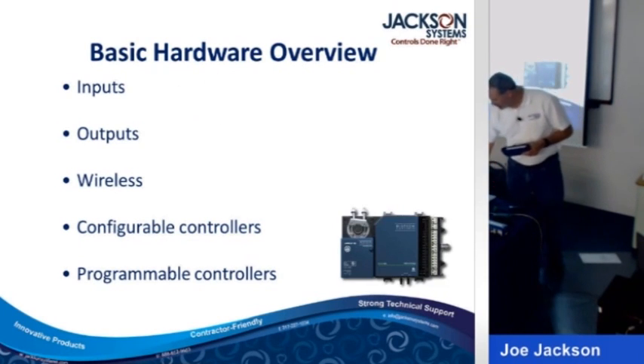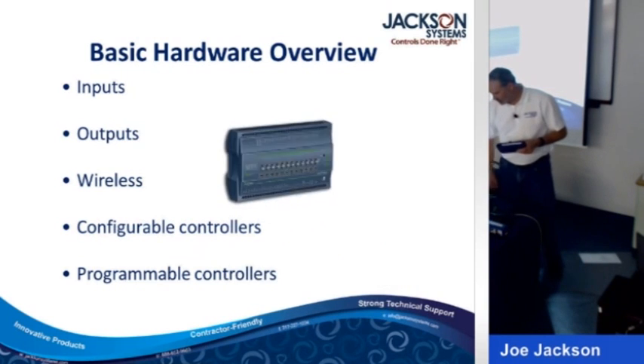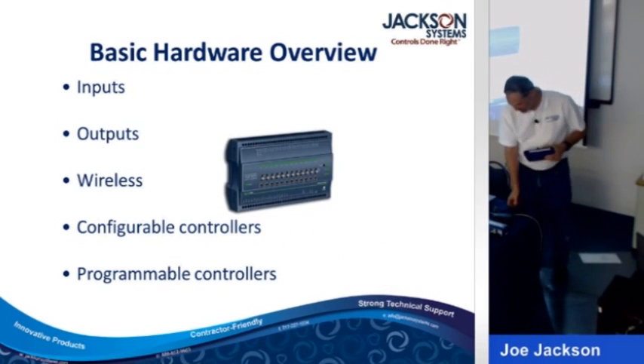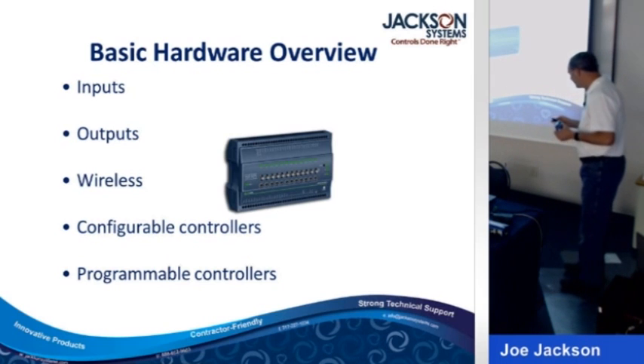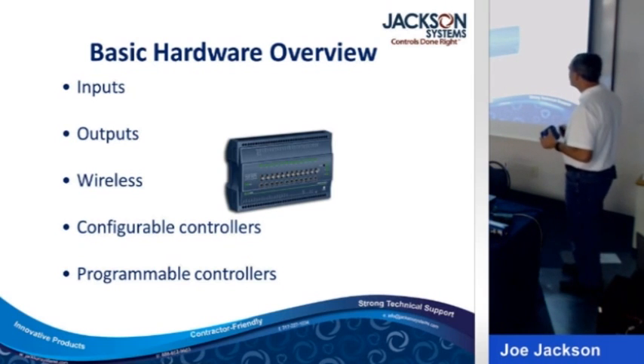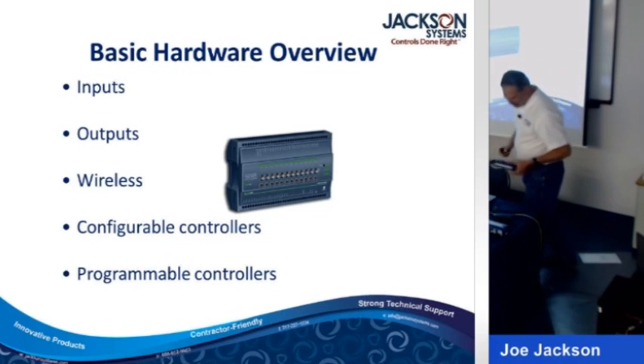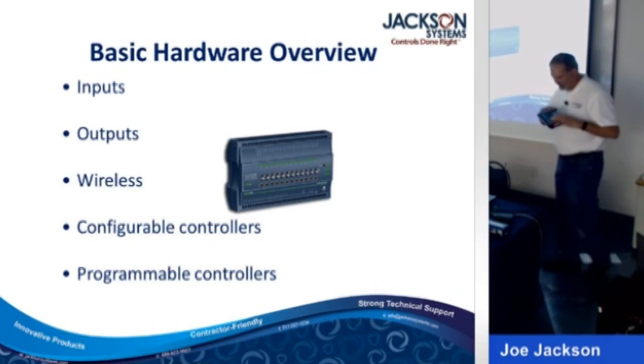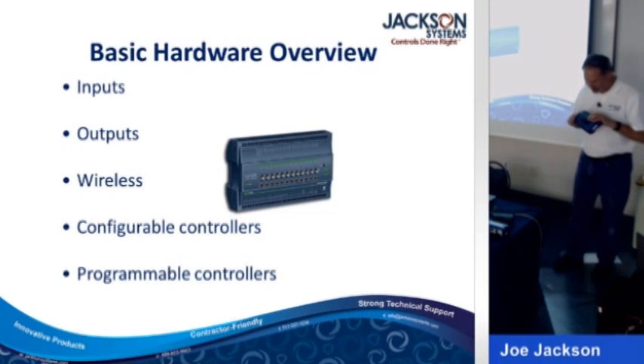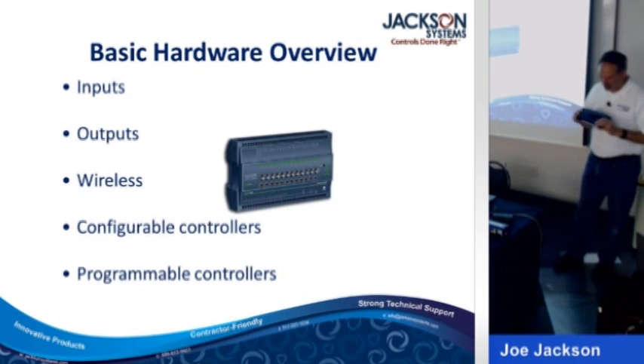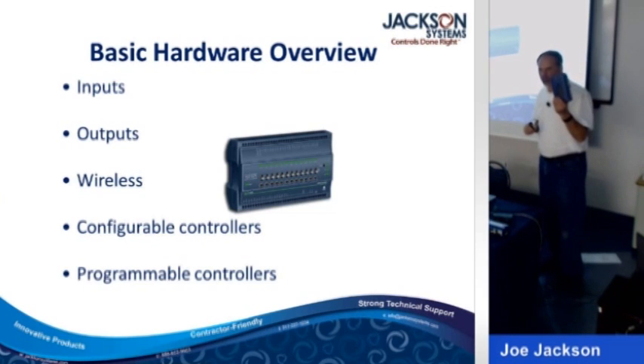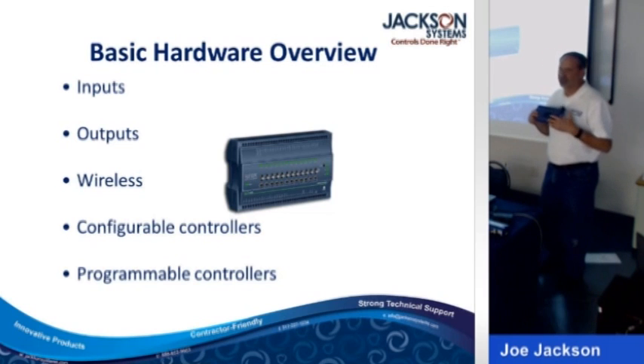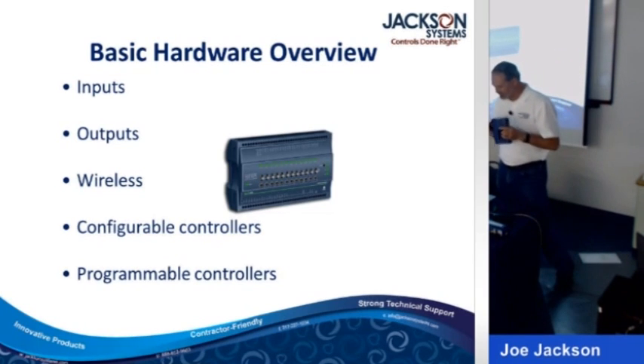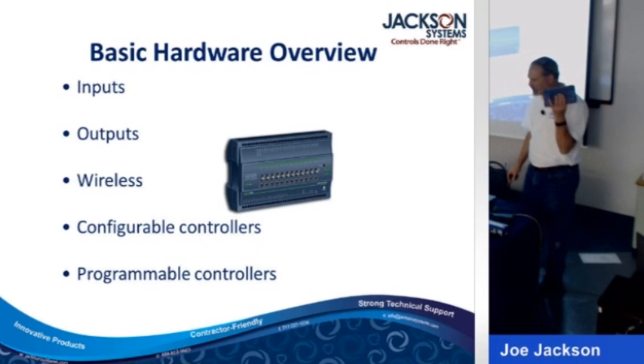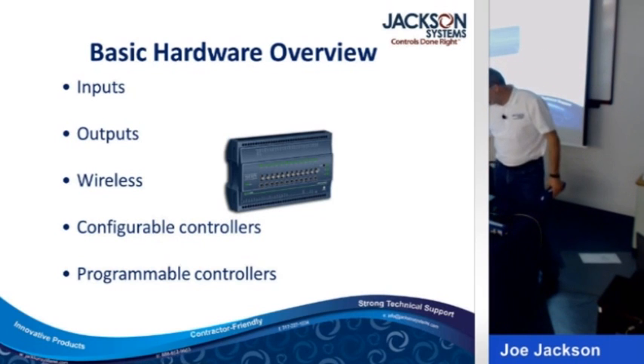That's a configurable VAV controller, programmable one. The one on this slide, they make them a couple different ways. These are hand-off-auto switches, so you can override things if you'd like to. The one that we've got here actually has a little LCD screen. It doesn't look like much from there, but it's actually really, really cool. You can override every single point in the controller. At a glance, it tells you what's overridden. It tells you if any of the sensors fail. It's all super easy to use, super friendly. It's really a nice feature. It costs an extra $100 to throw it on a controller, but well worth the $100.